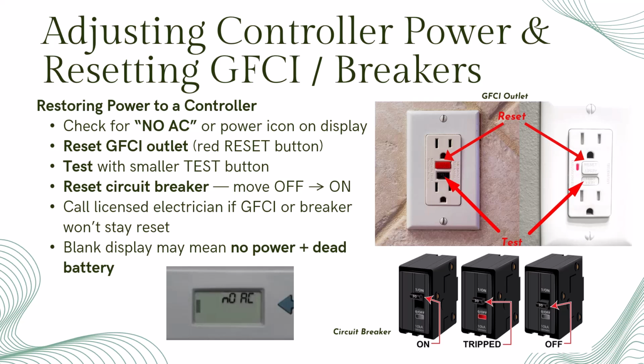Some models show red or green lights to indicate status. If it won't reset, check the outlet with the smaller test button or check for other dead outlets on the same line. If the issue isn't at the outlet, inspect the circuit breaker. A tripped breaker sits in the middle position. To reset it safely, move it fully to off, then back to on. If it doesn't hold, the breaker may be faulty and needs replacement by a licensed electrician.